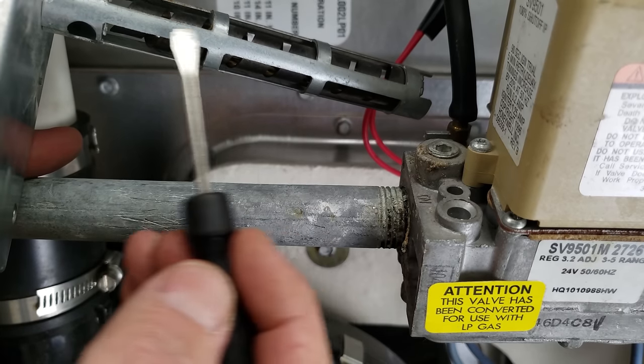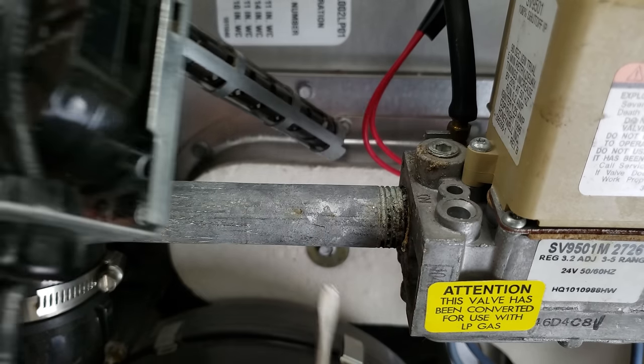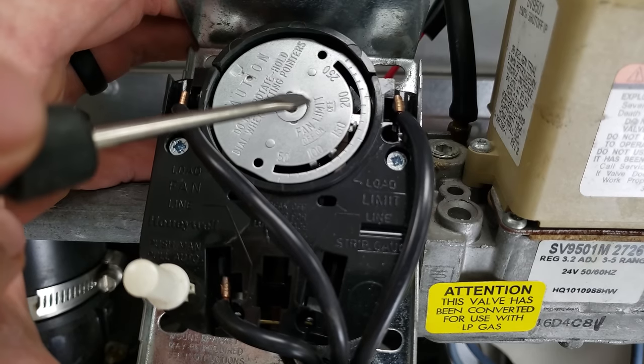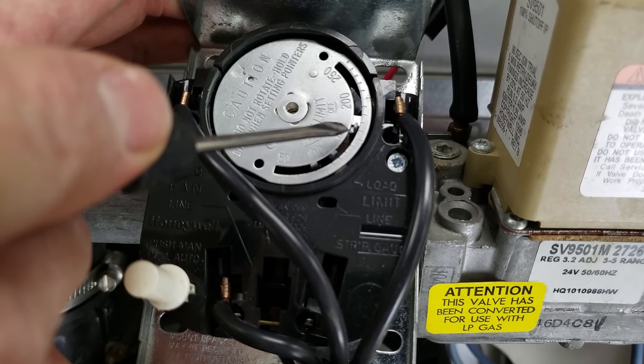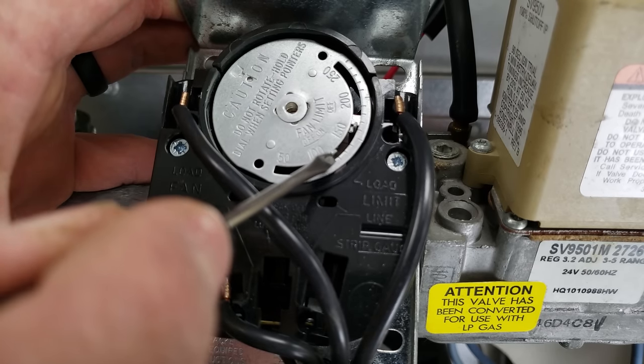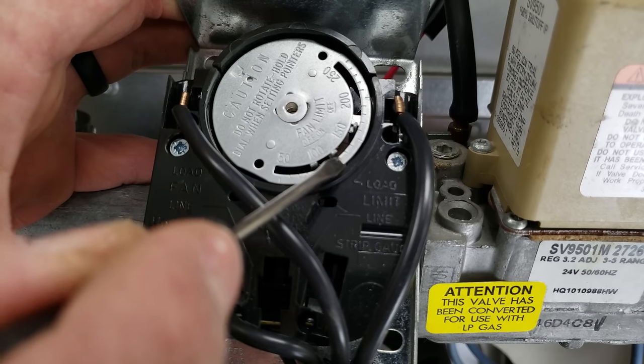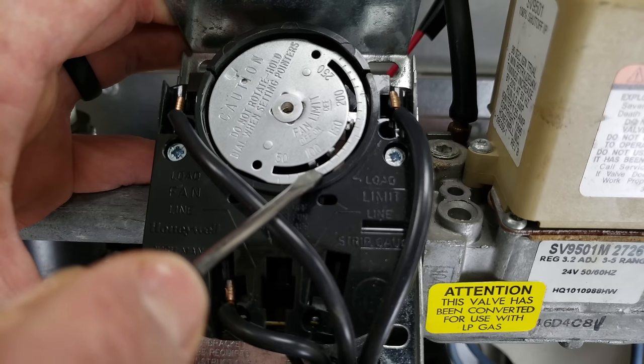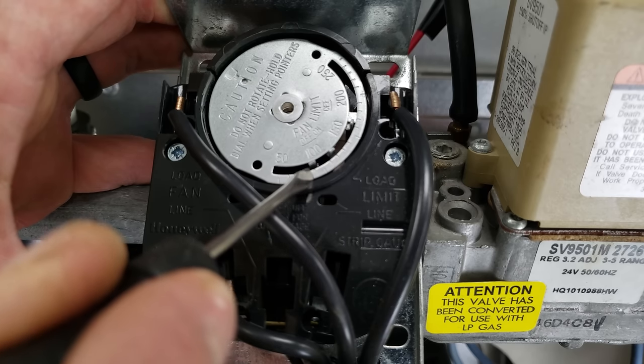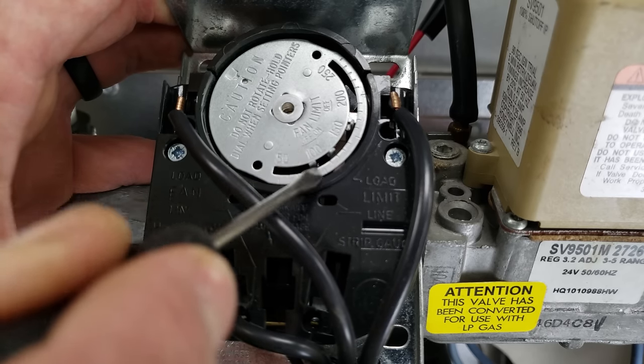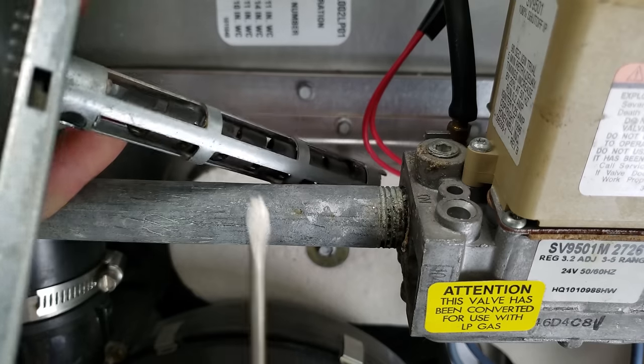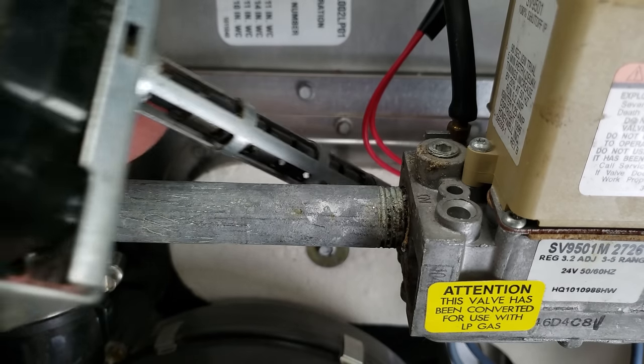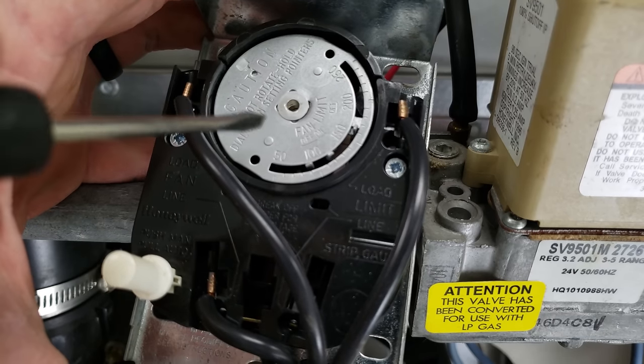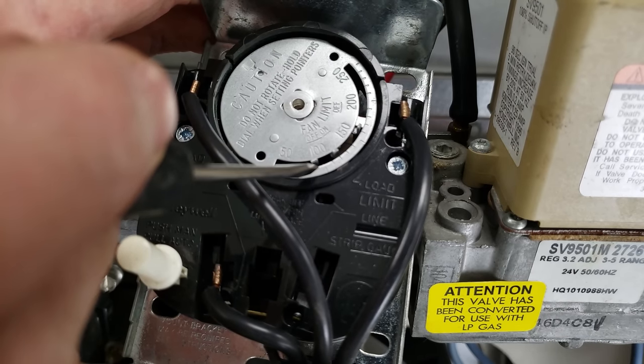So if this bimetal right here senses that the temperature is higher than 160 degrees, what's going to happen is the blower motor is going to continue to run, but it's going to shut off the gas. And this right here, you have it set at about 115 to 120, and that's when the blower motor turns on. And then right here, you should have this set for about 90 degrees. And so this is where our problem lies. Either this bimetal right here is worn out due to expansion and contraction, or this temperature right here is set down too low.